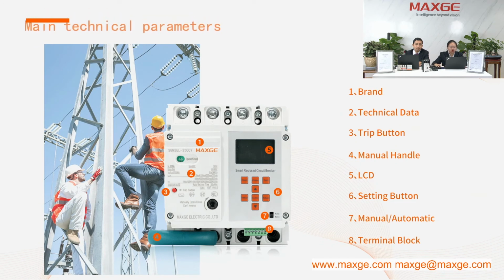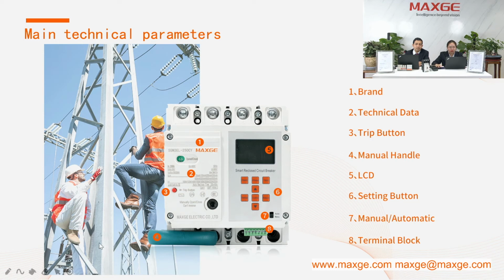Here is an introduction on the front side of our smart MCCB. Here is the terminal block. Terminal block is for connecting to the meters in the distribution box. Yes, and in the smart MCCB the motor is inbuilt, so no need to mount an external motor. So that motor can be connected to the terminal, and the MCCB can be turned on and off from a remote location. It has manual and automatic modes, and normally it is under automatic. Yeah. And under maintenance you need to change to the manual one, and it is easy for the operators to do the maintenance. Yes.